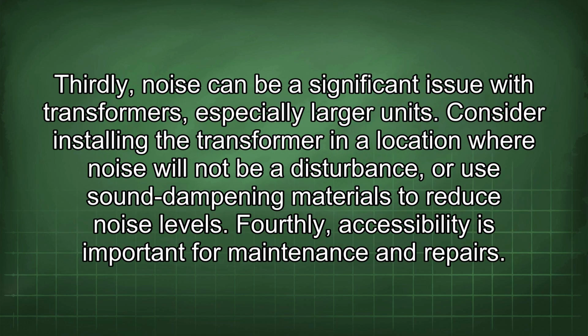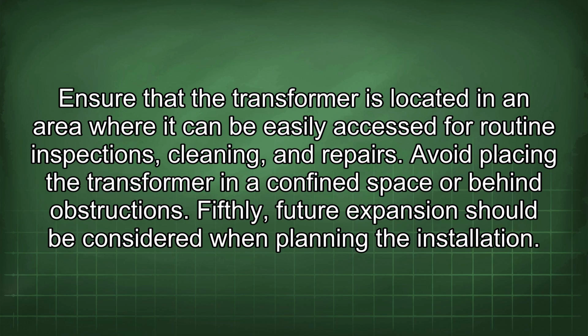Thirdly, noise can be a significant issue with transformers, especially larger units. Consider installing the transformer in a location where noise will not be a disturbance, or use sound dampening materials to reduce noise levels. Fourthly, accessibility is important for maintenance and repairs. Ensure that the transformer is located in an area where it can be easily accessed for routine inspections, cleaning, and repairs. Avoid placing the transformer in a confined space or behind obstructions.